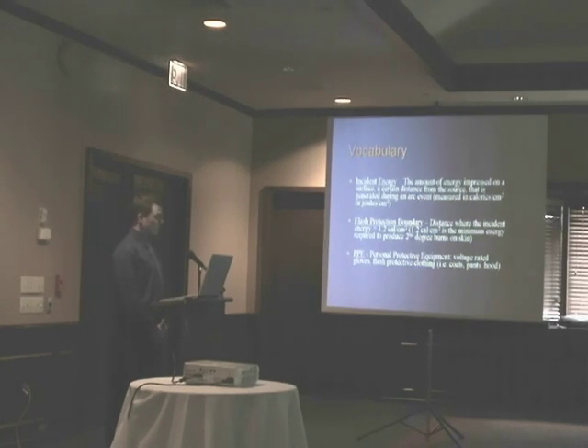Continuing on with vocabulary, the incident energy. Now, this is the amount of energy impressed on a surface, a certain distance from a source, that is generated during an arc event. This is measured in calories per centimeter squared or joules per centimeter squared. In our flash hazard analysis, we use calories per centimeter squared, but it's just a conversion factor to get to joules per centimeter squared. Also, you have the flash protection boundary. This is the distance where the incident energy equals 1.2 calories per centimeter squared. This is the minimum energy that is required to produce a second-degree burn on someone.